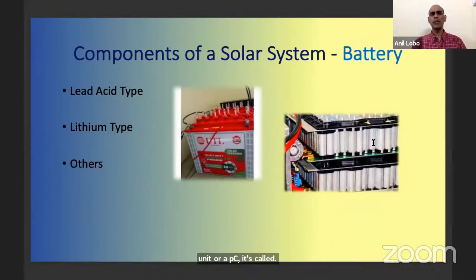So these are the two types of batteries. The most common battery that we use in the solar system is the lead acid battery. The lead acid battery comes in different ratings. We have the C20, the C10, the C5 ratings. Choose the right battery. Sit with your system integrator and see what battery you need based on your application. If you're going to have lights and fans and television and you're going to have a very nominal load, you might need a smaller battery, and it might be a sealed lead acid battery or even one of the float batteries, the liquid batteries. Whereas if you're running your air conditioners, if you're running heavy equipment such as geysers, water heaters, pumps, and so forth, you need to have a deep cycle lead acid battery. Batteries that can have quick charge, quick discharge, a good battery management system.